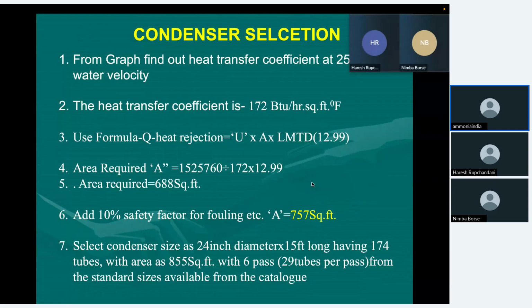So from the graph, the heat transfer coefficient was approximate; the actual is 172 BTU per hour per square foot per degree Fahrenheit. So the area required becomes total heat rejection divided by U into LMTD. Area required is 688 square feet. Add a 10% safety factor for fouling, etc. So 757 square feet.